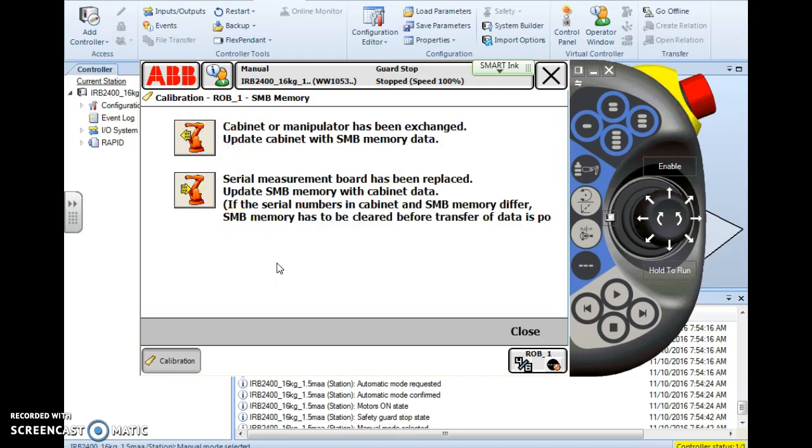The bottom option: the SMB serial measurement board has been replaced or the battery's dead or there's some type of malfunction. With the second option, we can update the SMB memory with the cabinet data. So basically we're transferring or copying the values from the cabinet or the PC to the SMB, and it's a pretty easy process.